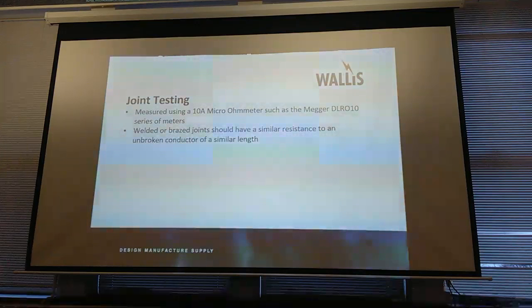You need to know that these joints are sound, and we are talking, you know, the joint should have a resistance that is similar to an unbroken length of copper. So if you've got a copper strip, a meter long, and it is 100 microohms or something like that, and then you've got a joint in it, you need to make sure that joint is good enough so that it is still 100-ish microohms. So you're actually looking across a joint somewhere in the region of 50 microohms, something along those lines.